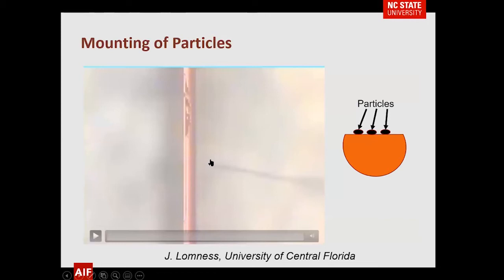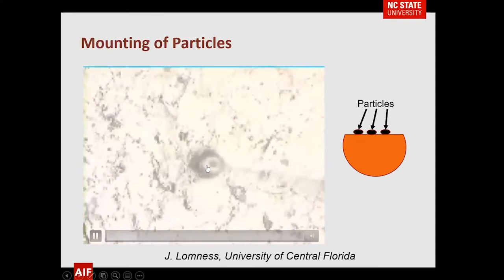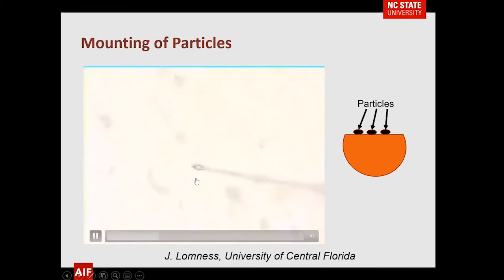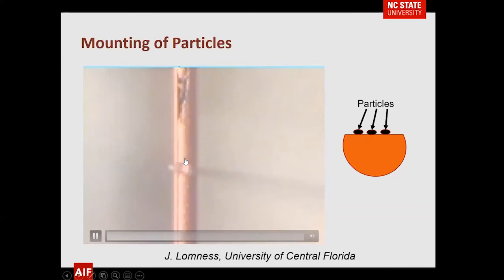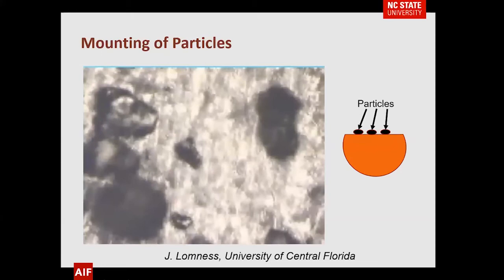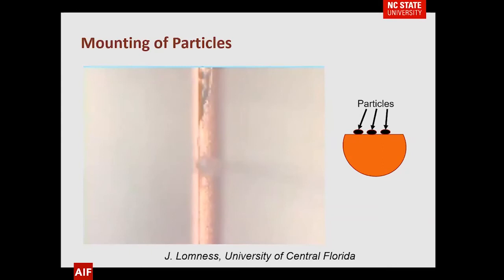Here's another mounting method. One of Lucille's students, Jan, wanted to look at particles. Using actual epoxy, she dips the needle into it, spreads it on top of the grid, and then goes over with epoxy on the tip — making it easy to pick up a particle. She brings the particle over and deposits it directly on the grid. There's no lift-out; you're simply placing particles directly on the grid for final thinning. We've used this successfully at NC State for particles used in 3D printing.